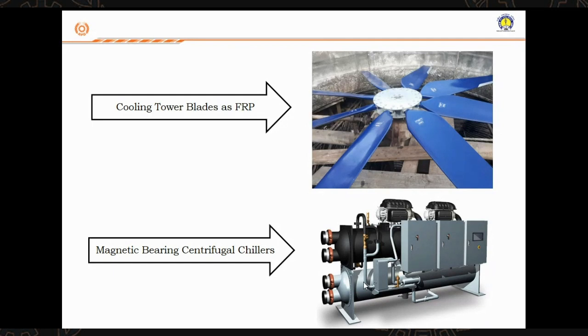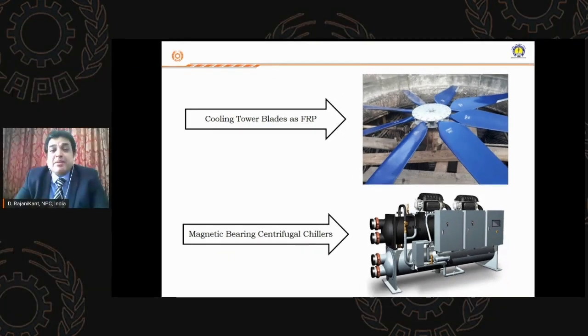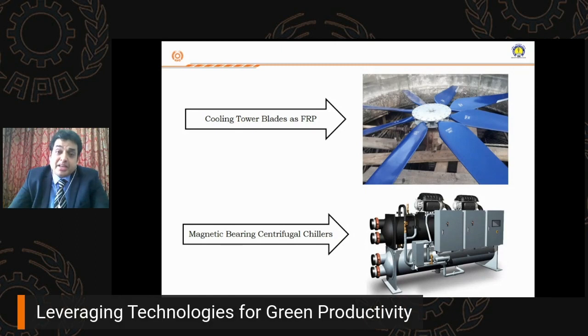If you see the conventional cooling tower in SMEs, they have metal blades. The cooling tower fan will have metal blades, and nowadays you have FRP blades. This is called fiber reinforced plastic blades. The energy will be reduced by 30%. You can see that this is a proven technology, implemented even in some of the SMEs which are capable of investing on their own, by their own fund, capex.